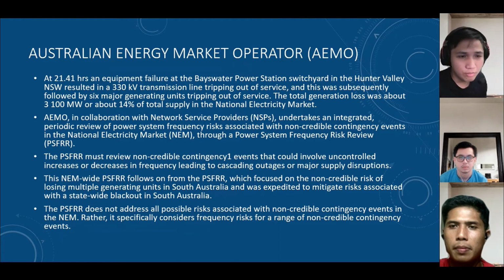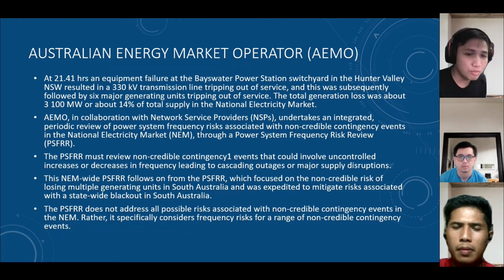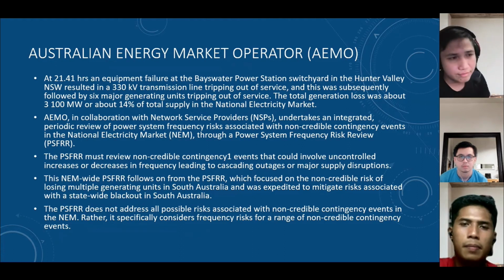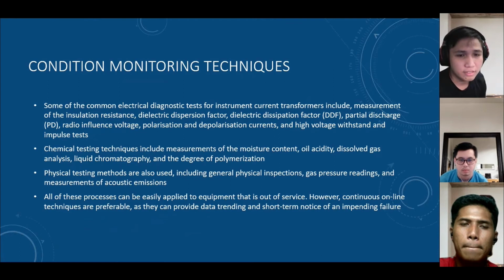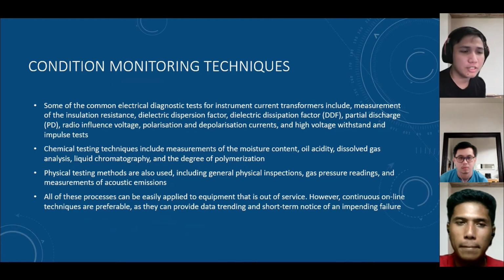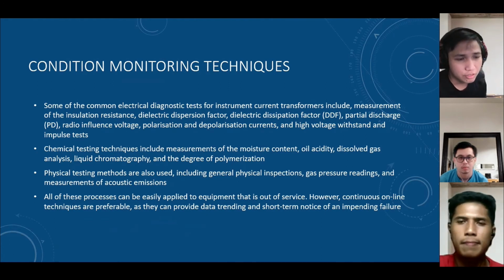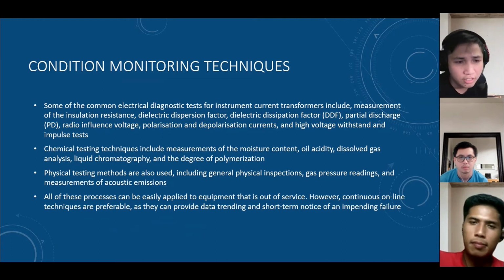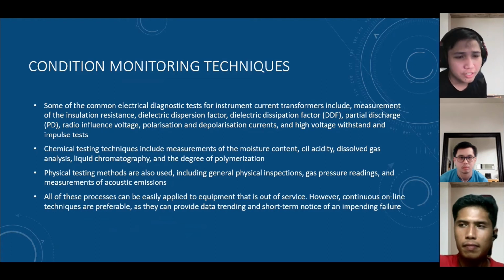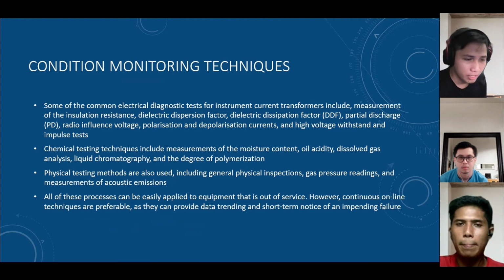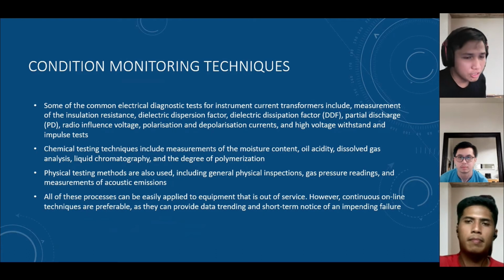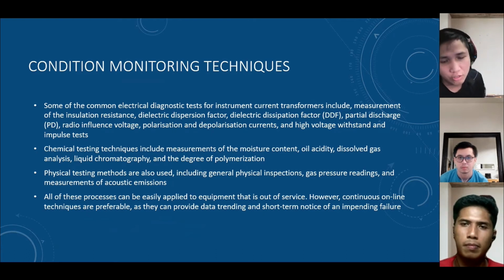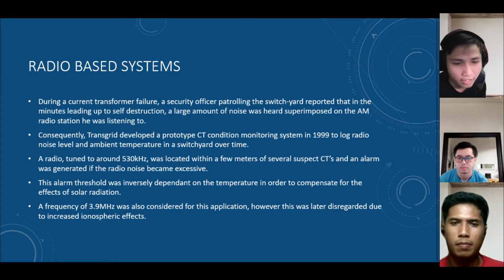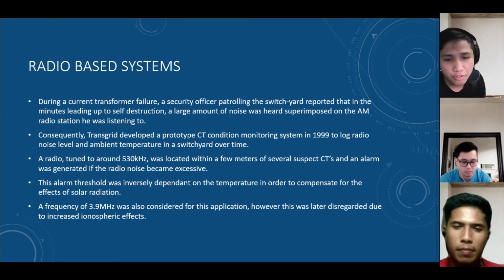So then, moving to the next one: what has been or will be done to prevent this event from happening. Next slide. With the collaboration, there are three methods to prevent this from happening again. The first is to enhance condition monitoring techniques: inspection, chemical testing for each component of the transformer, and physical testing methods. All these processes can easily be applied to equipment that is out of service. However, continuous online techniques are preferable, as they can provide data trending and short-term notice of an impending failure.